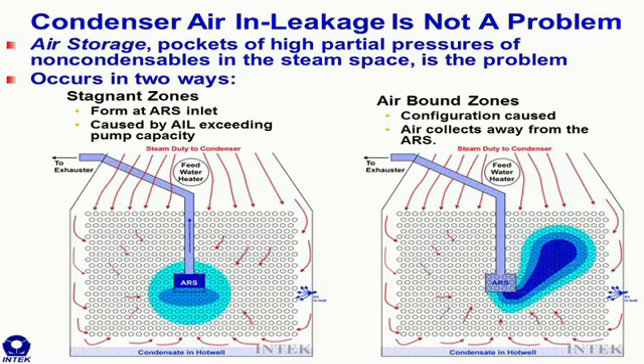Now, in both types of air storage, if the tube is located in an air storage zone, then the cooling water enters the tube in the inlet water box, travels through the tube, condenses very little to no steam, and exits the tube well below the expected value. And so that array of temperature and flow sensors that I showed on the previous slide, those are installed on the outlet tube sheet and provide measurement of these air-bound zones. In the next few slides, I'll show measurements from operating condensers that clearly show these air-bound zones.